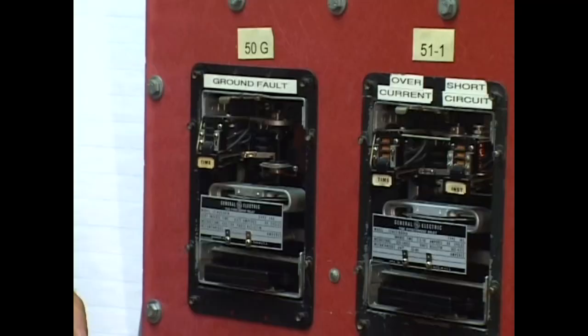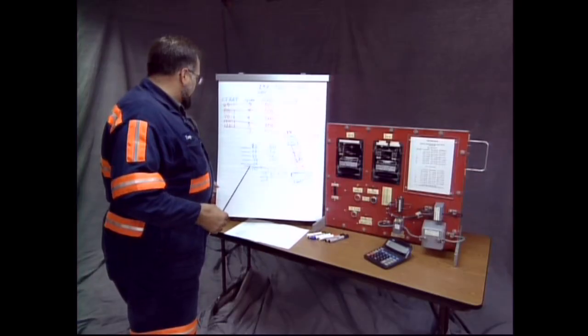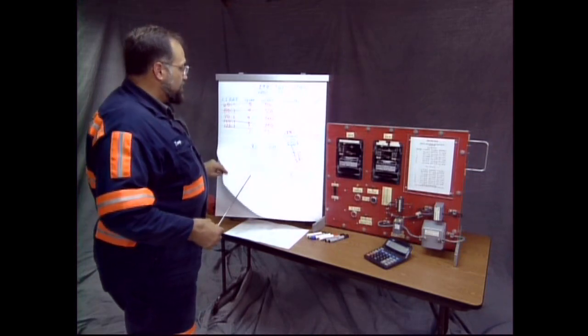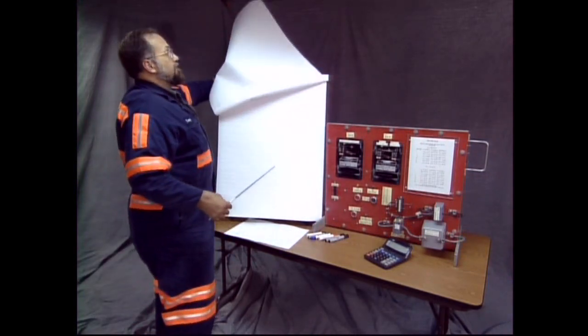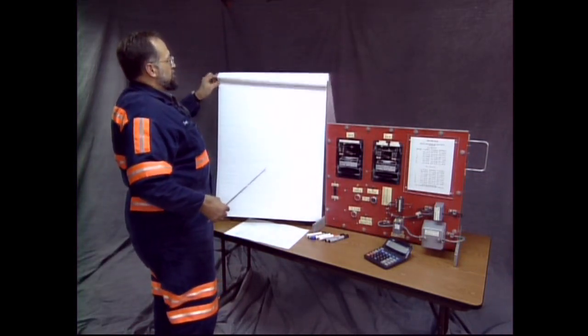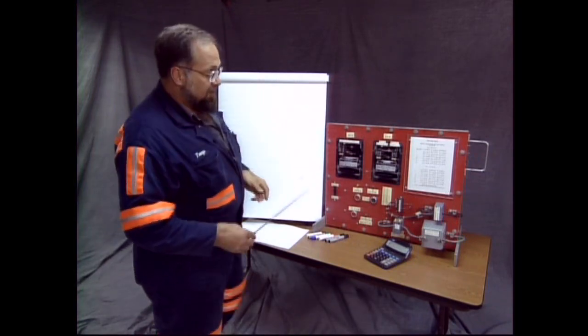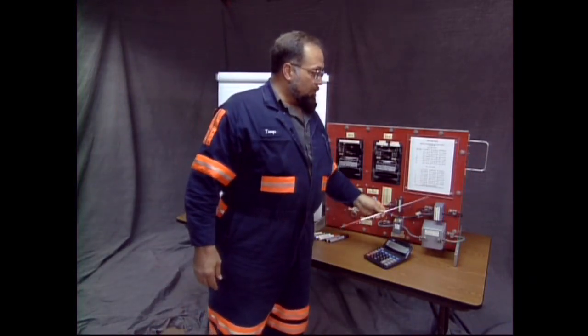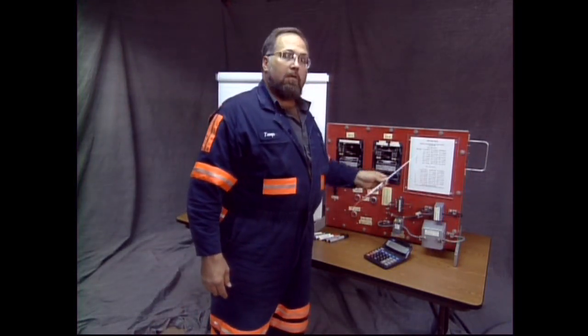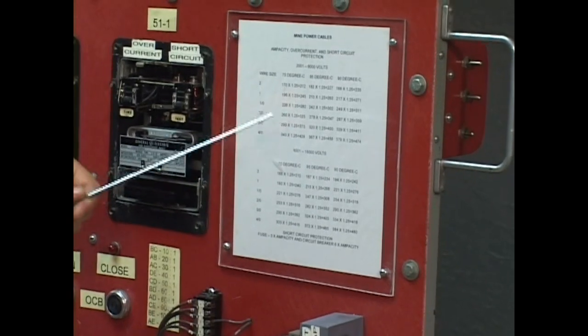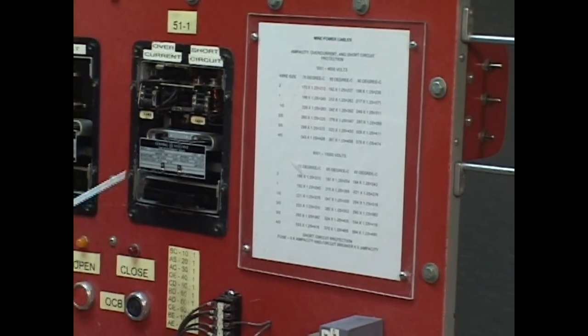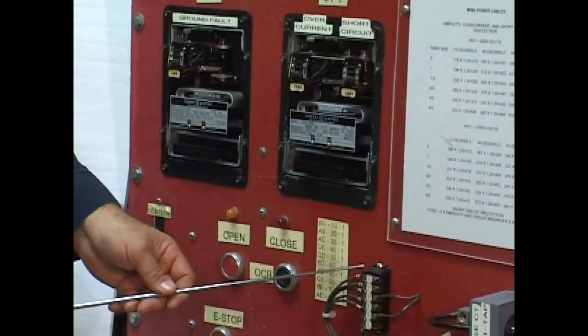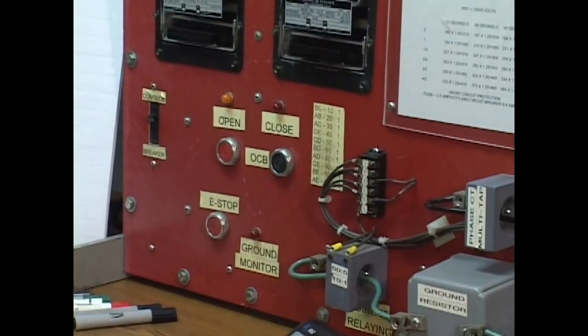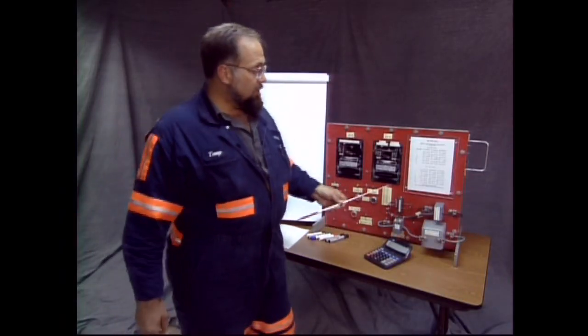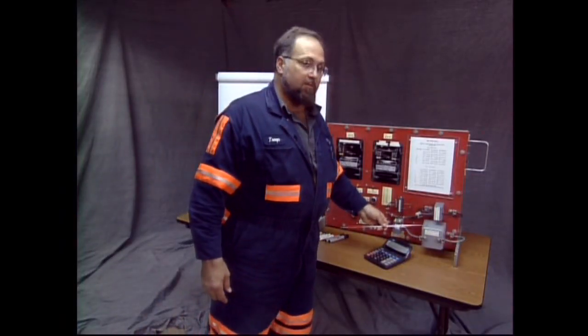This one, 50G, we also have to adjust, and it requires a little math too, a very little math. Now, as I said earlier, we find our levels of adjustment for different cables on this chart, adjust the relay and the CT ratio to accommodate a cable. On this one, there's only one calculation.